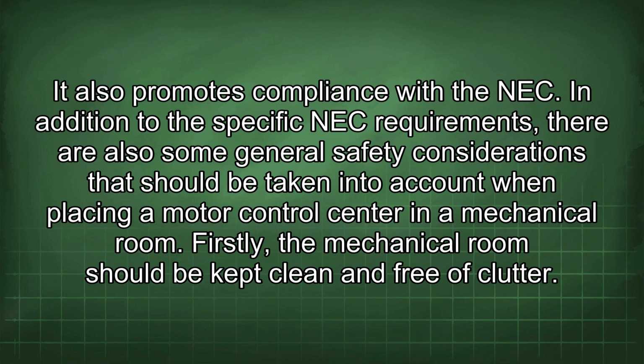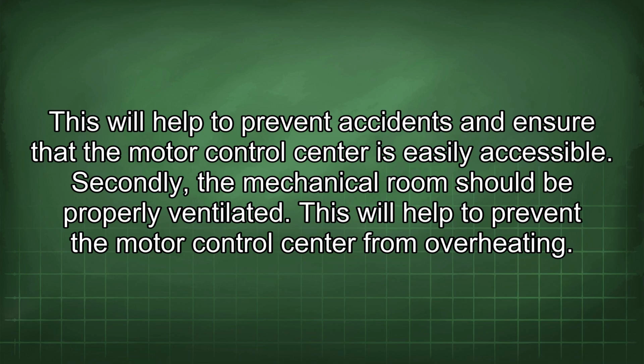In addition to the specific NEC requirements, there are also some general safety considerations that should be taken into account when placing a motor control center in a mechanical room. Firstly, the mechanical room should be kept clean and free of clutter. This will help to prevent accidents and ensure that the motor control center is easily accessible. Secondly, the mechanical room should be properly ventilated. This will help to prevent the motor control center from overheating.